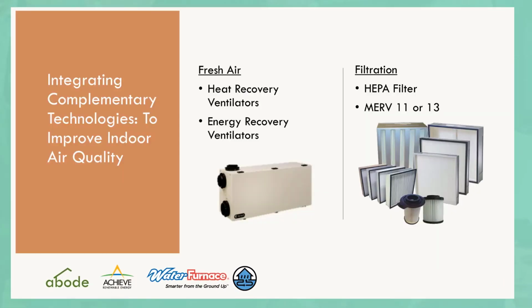And then integrating with other modern technologies like mechanical ventilation or high-level filtration is easy with a geothermal system, at least a ducted one. You can't really put an ERV onto a hydronic system, of course, but with the ducted systems, it's quite easy to run the HRV and have an integrated set of controls for the two technologies. The standard filtration on most of the geothermal heat pumps is MERV 11 or 13, but they can be ordered with everything up through HEPA filtration.